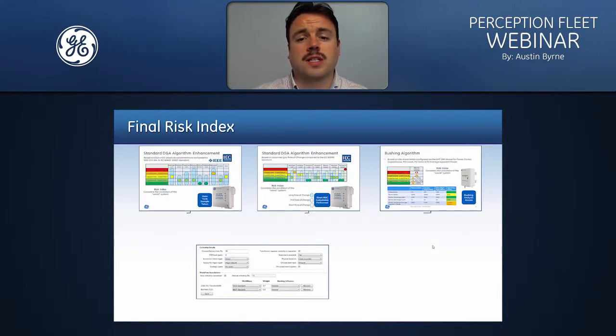The final risk index for the assets then is calculated for each individual algorithm. So a transformer or an asset within Perception can have multiple algorithms assigned to it. Those algorithms are then run through the analytics engine to come up with a separate risk index for each of the algorithms. But in order to have a simple final risk score for the asset, we take all that information, we run it through the analytics engine, we look at the criticality details for the asset, and then we come up with a final risk score.